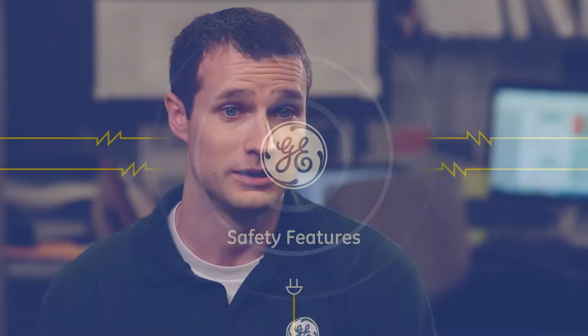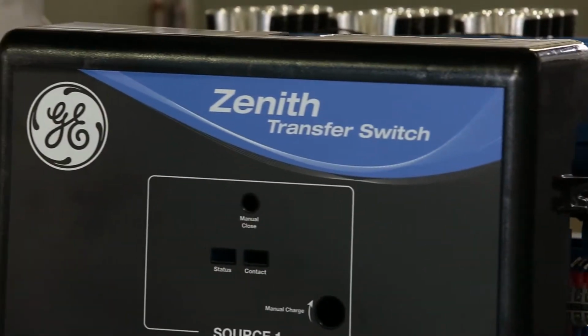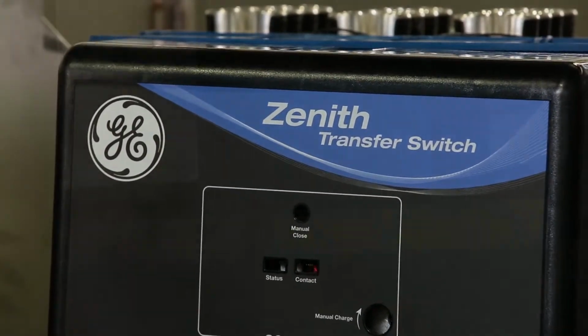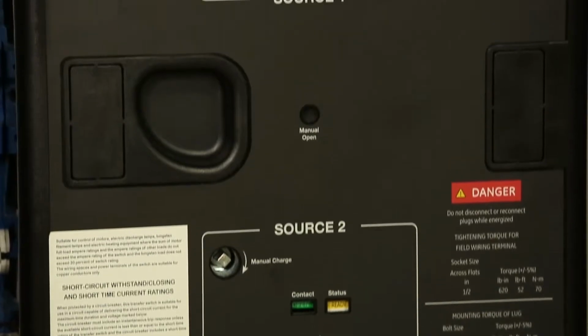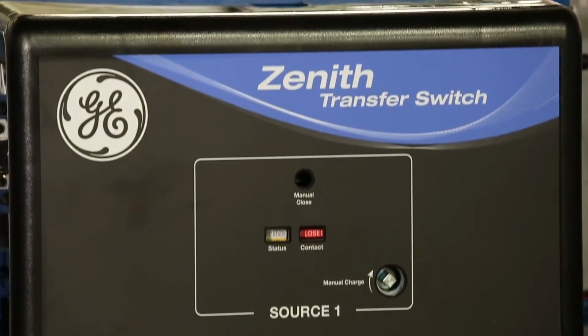We have to ensure our product meets third-party safety standards like UL 1008, as well as our own GE safety standards. Some of the safety considerations we put into this new ZT30 product include the ability for the user to operate it without having to open the front door, both in the ATS configuration and the bypassing configuration, so you have a built-in protective barrier.